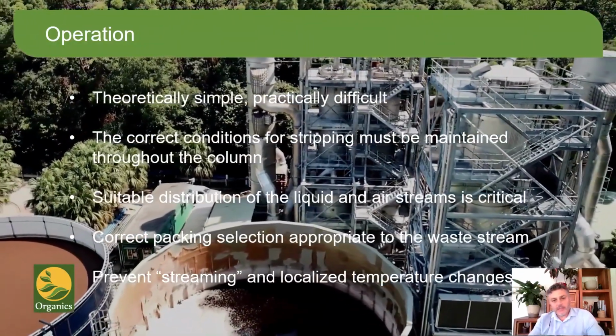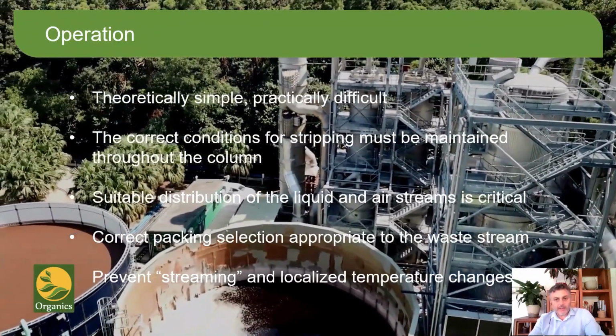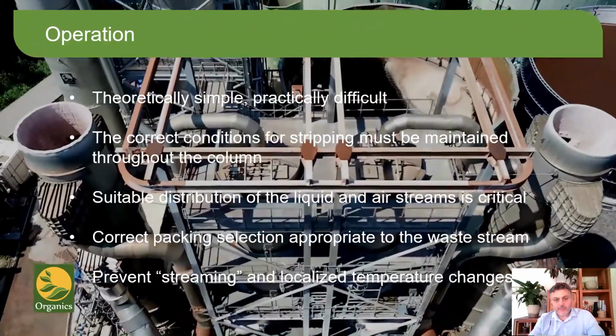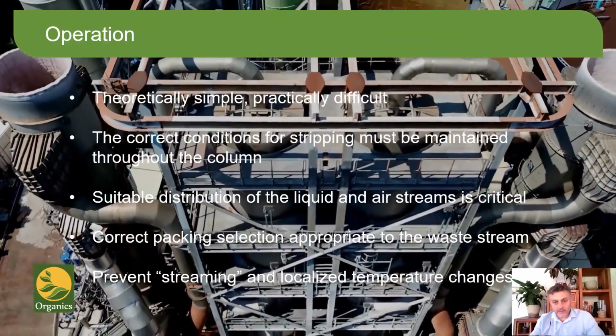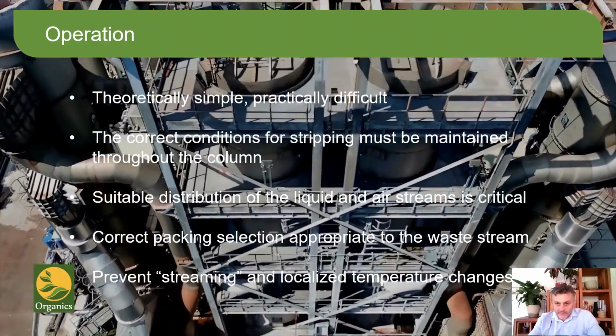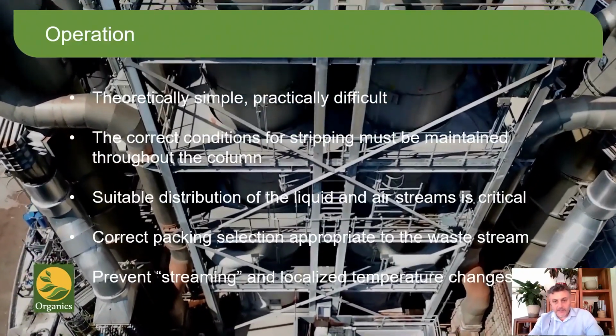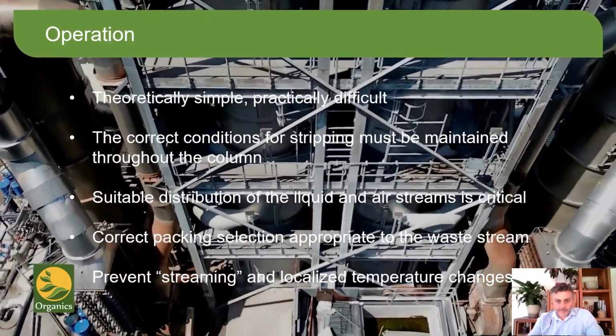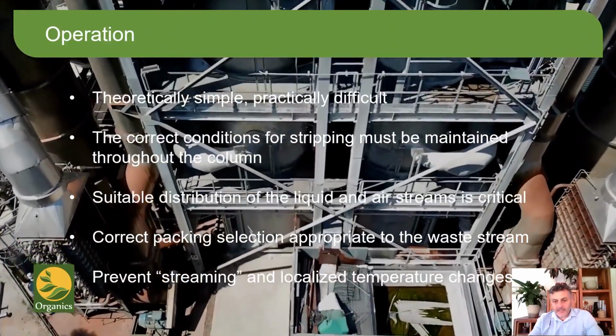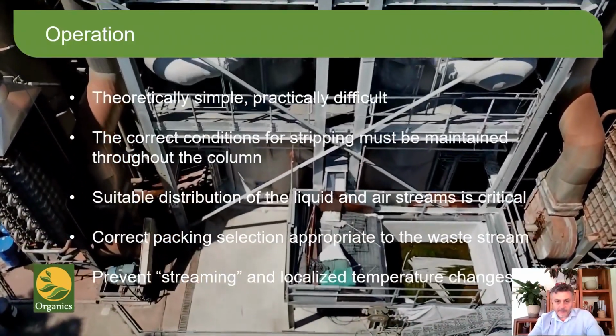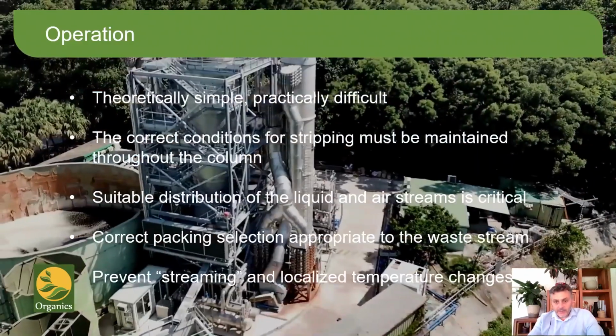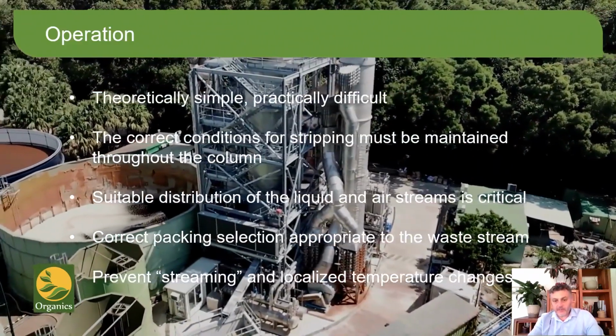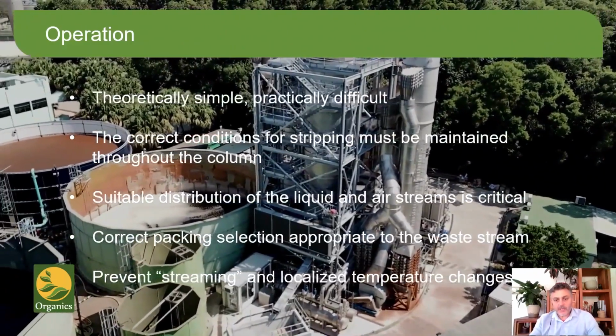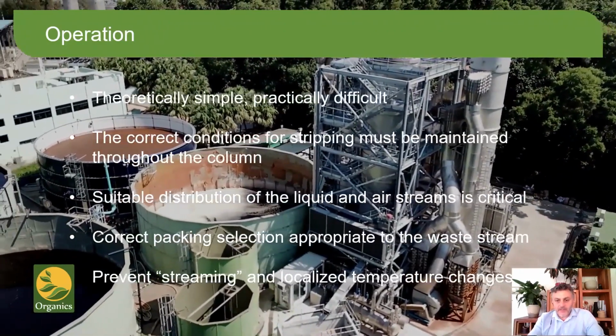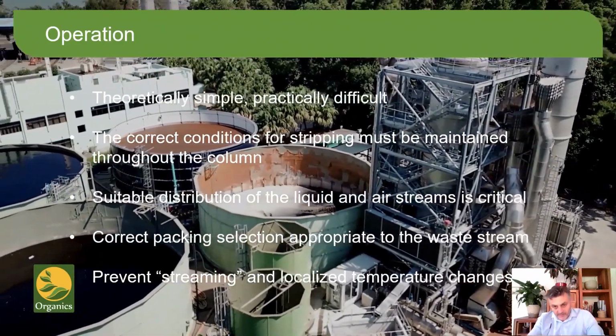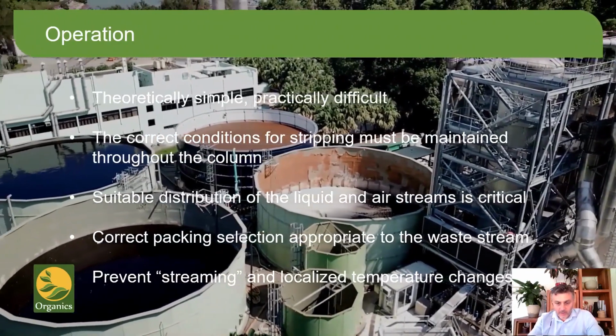But within the stripper column itself, it is critical to ensure the two streams of water and air interact correctly. The liquid distribution must be good enough to ensure the whole width of the column is used, but robust enough not to block. We have developed our own trough and notch distribution that has stood the test of time, and our redistribution systems that prevent the liquid from moving to the walls has allowed the columns to be as tall as we need them to be. Our air heating system is also unique with its external mixing duct to ensure the most efficient use of steam. Then, once the two streams are correctly heated and distributed, we spend a lot of time developing and establishing the correct packing material that provides the best surface area to volume ratio without blocking.